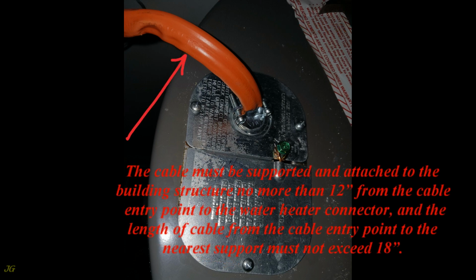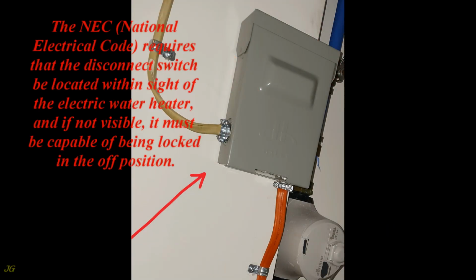The cable must be supported and attached to the building structure no more than 12 inches from the cable entry point to the water heater connector, and the length of cable from the cable entry point to the nearest support must not exceed 18 inches. The NEC, National Electrical Code, requires that the disconnect switch be located within sight of the electric water heater, and if not visible, it must be capable of being locked in the off position.